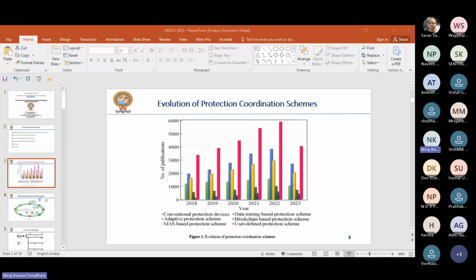So the main reason is that the power system is continuously changing day by day. Every day there is some advancement in the power sector, mainly in terms of the integration of different types of renewable energy sources. And when you go for integration of DGs at such a mass level, there is a topological change in the system, which requires that your protection schemes as well as systems be adaptive in nature. With the addition of each individual source, you will have an increased fault current level in the system. So you need a protection scheme where you can adjust the parameters of the relays as per your requirement and the system configuration, right?